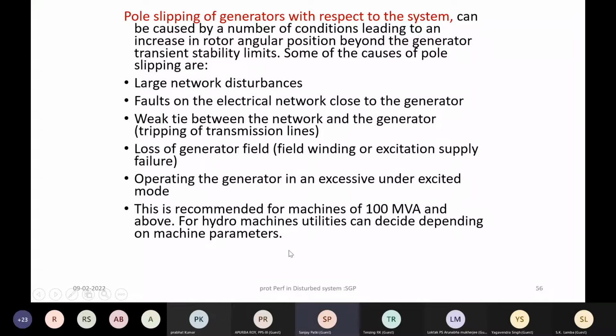Now, there is a question whether pole slip protection is really needed for all types of generators, because the capability of the generator to withstand asynchronous operation varies. One of the parameters which governs this is again the short circuit ratio, which we discussed yesterday. A short circuit ratio for a thermal machine of less than 0.5 obviously means that its ability to withstand short circuits as well as asynchronous operation will be limited. Hydro generators, which have a short circuit ratio close to 1 or even more than 1, are more robust, they are bigger in size, and they have better ability to withstand electromechanical forces created due to a pole slip condition.